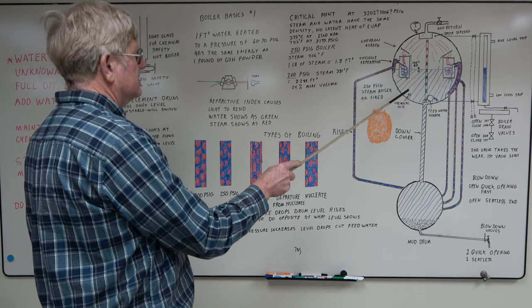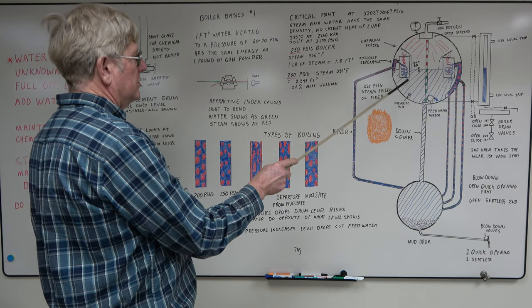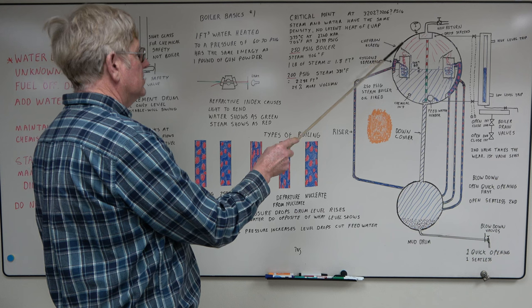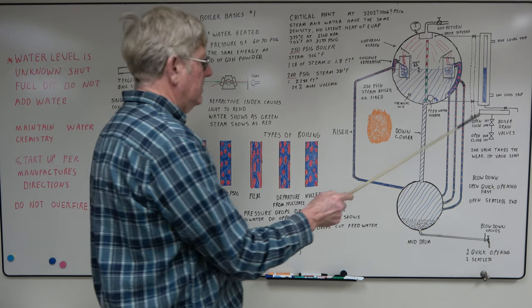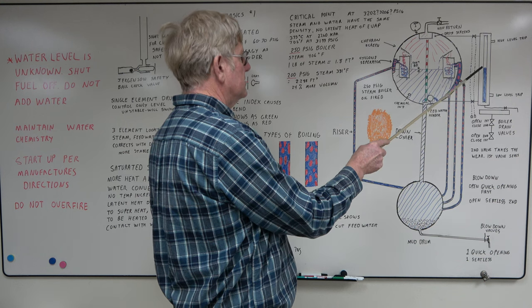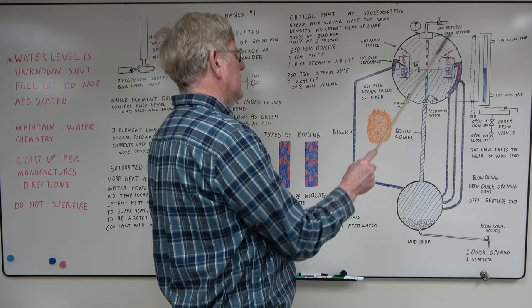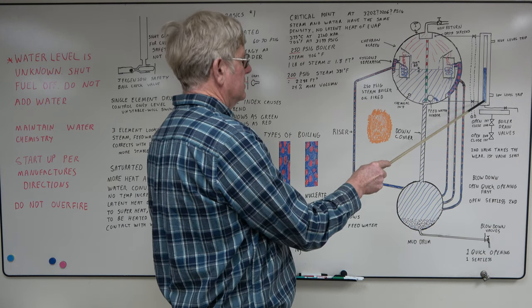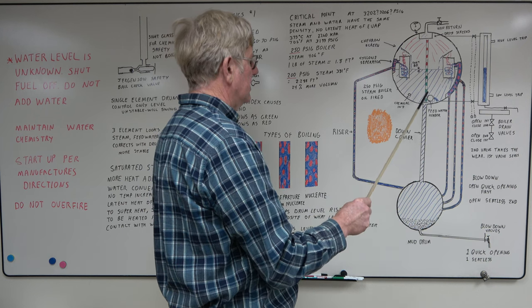I really like the bicolor glasses. You can see these a long ways away. There's no question of where the level is. You walk up on these a lot of times they're dirty, it's hard to see the level. These are no question. It's a little better deal for operators.